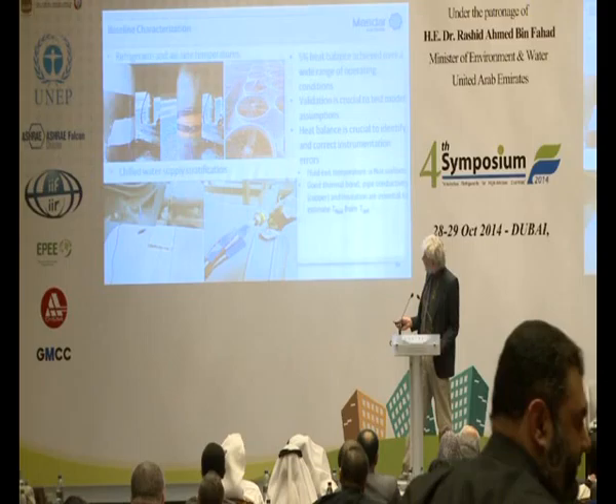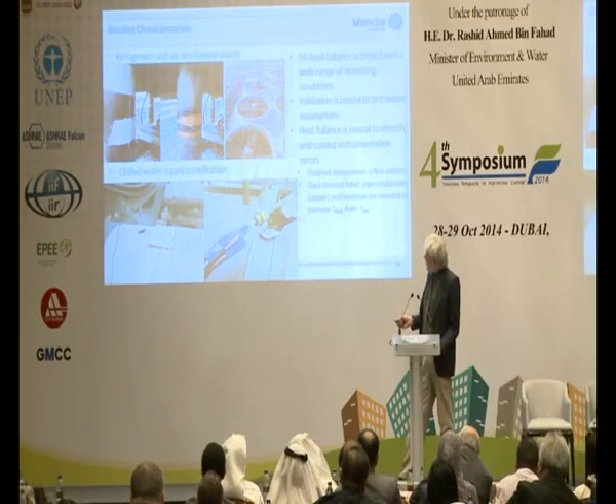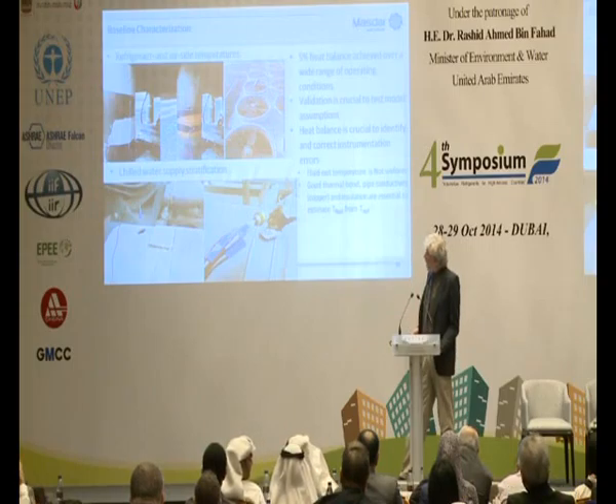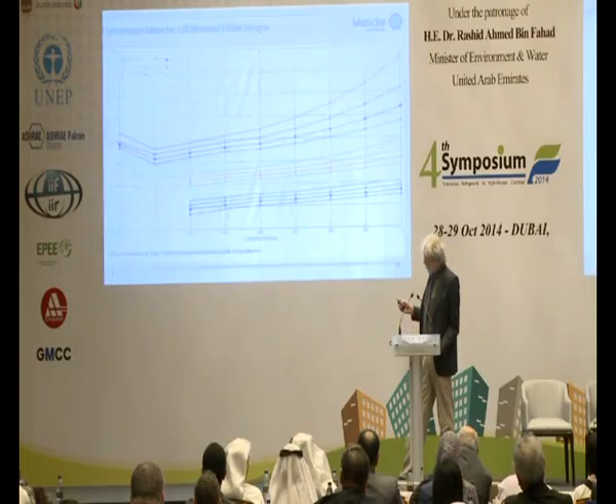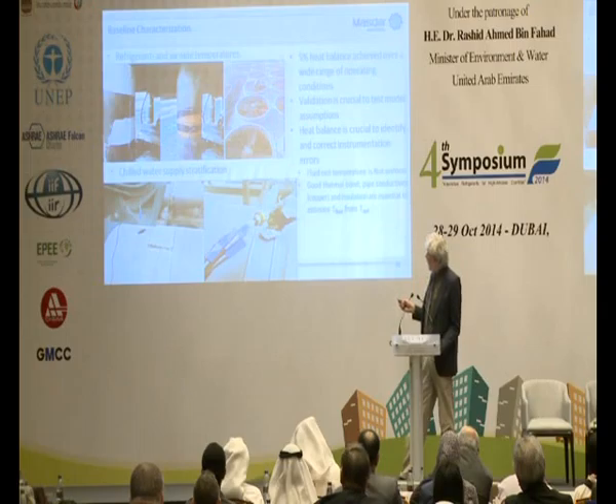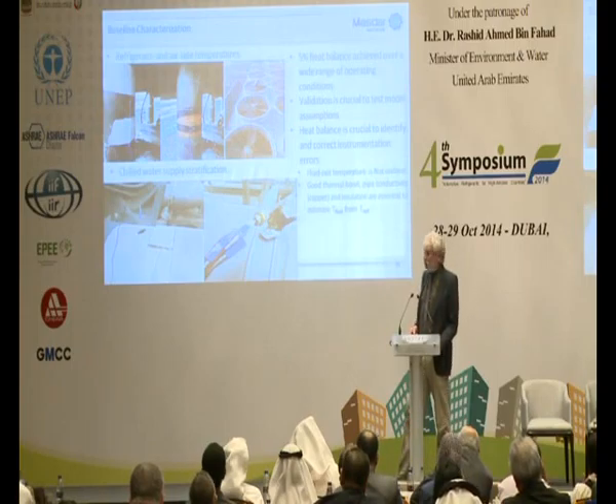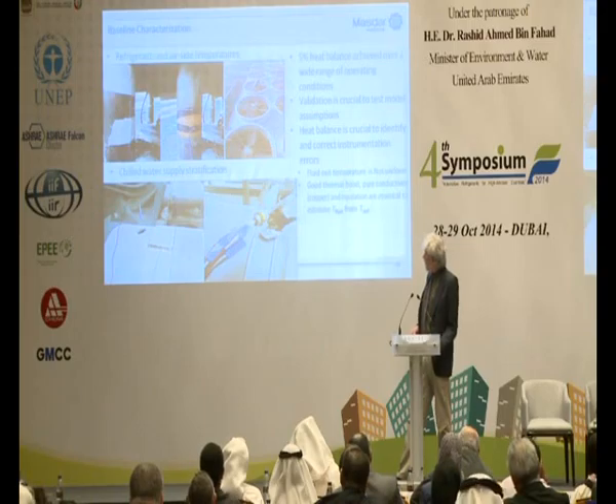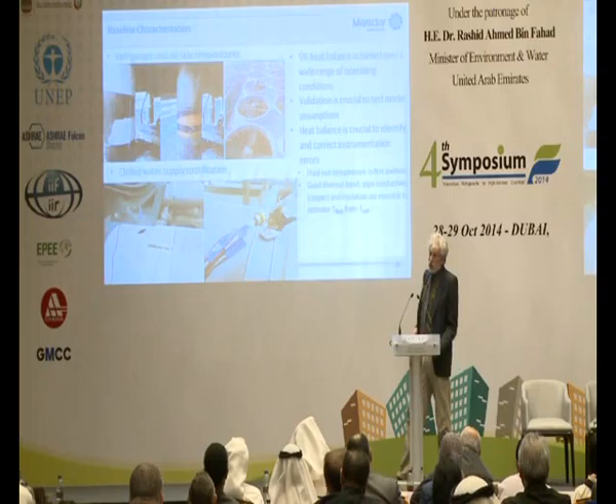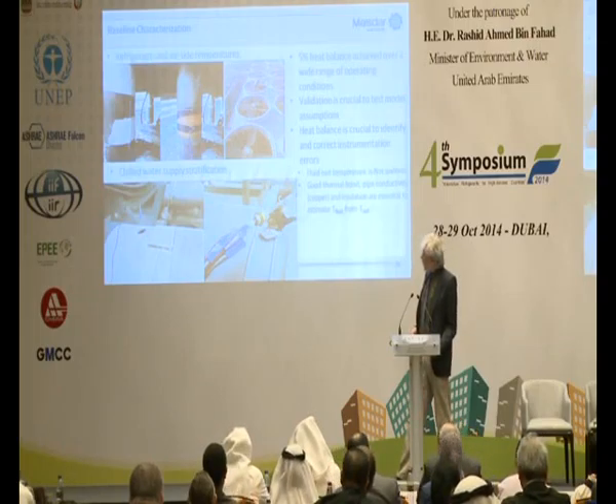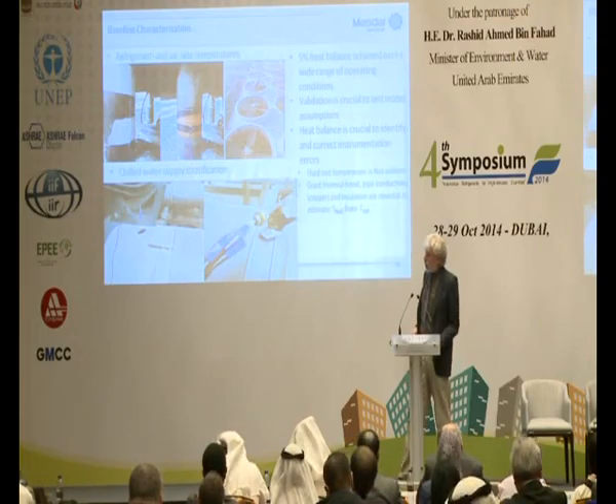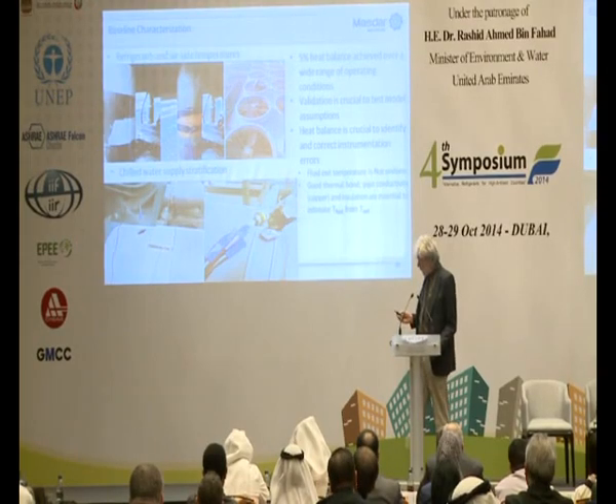Just some other measurements and some surprises. Generally, we measure refrigerant conditions with plugging pressure transducers directly into service ports, measuring suction and discharge pipe surface temperatures, which works rather well if it's done properly. But some other things are challenging. We found that the temperature distribution on the condenser discharge is not what we'd like to assume, which is uniform, and therefore we have to have distributed arrays of thermocouples to measure the temperature rise through the condenser on the air side accurately. Similarly, on the water side, there's quite a bit of stratification in the chilled water supply line, so we had to deal with that.